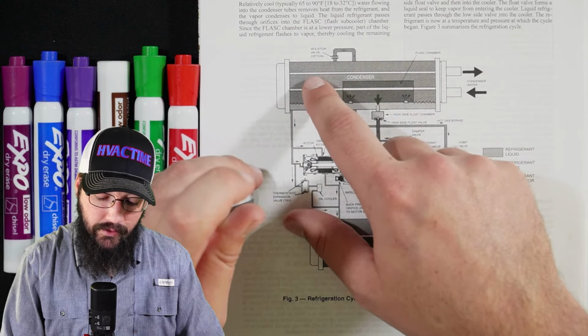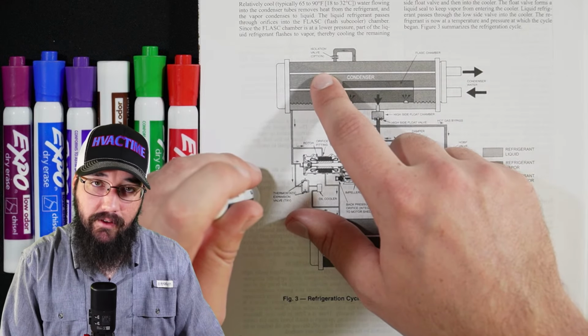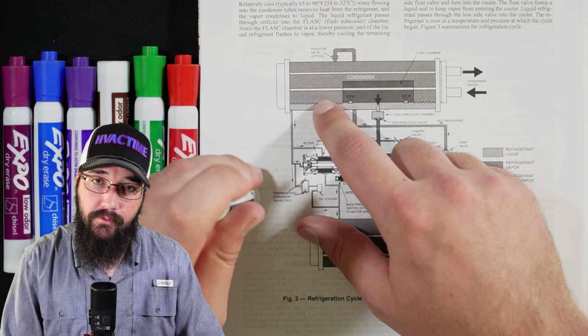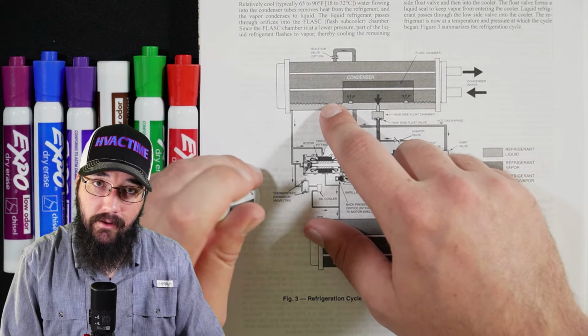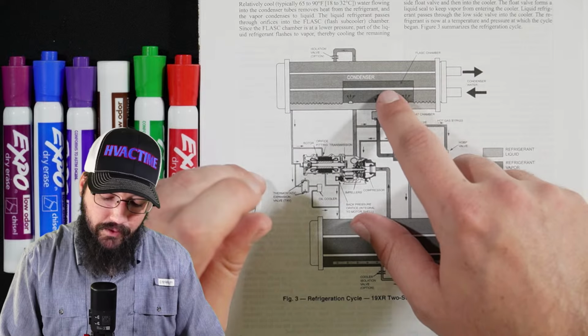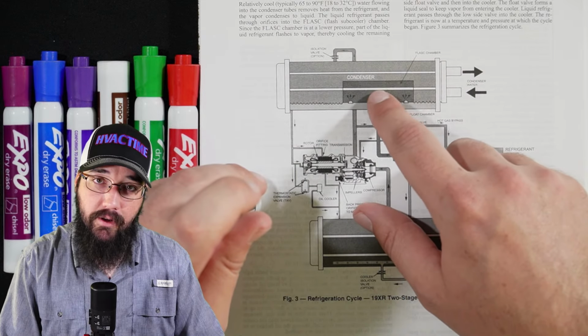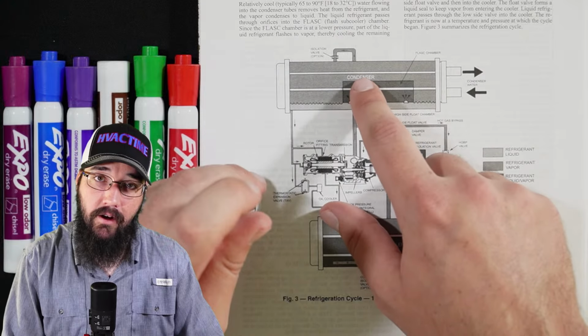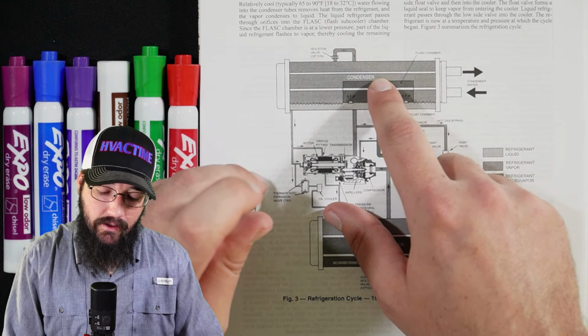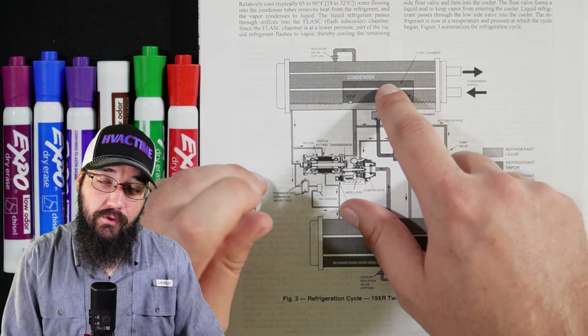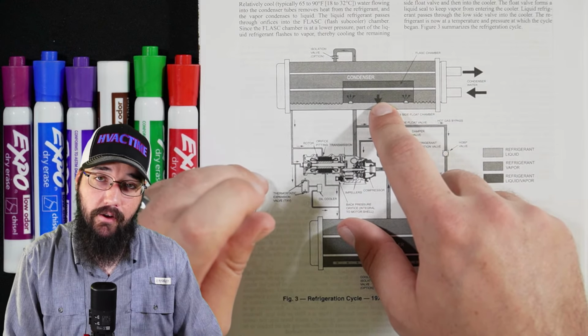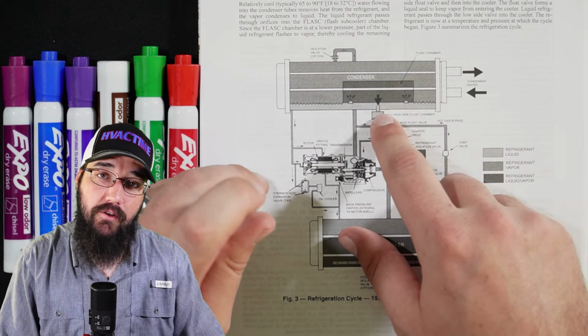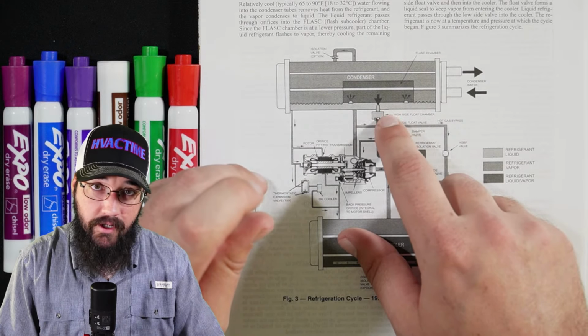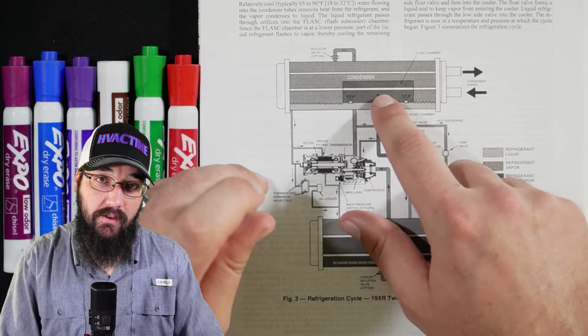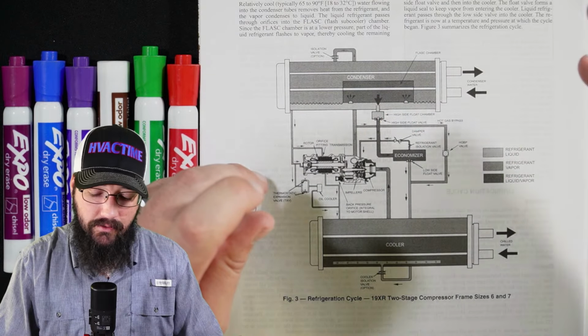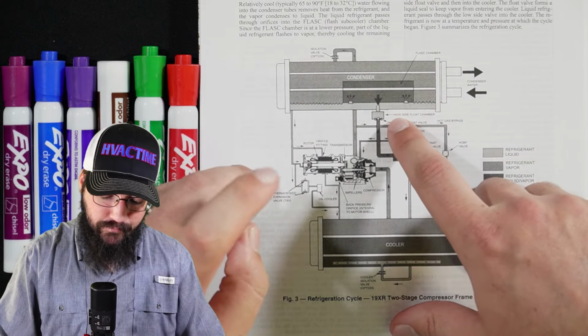So not only is the outside of this chamber condensing that liquid refrigerant down from a high pressure discharge gas to a high pressure liquid, but then we're also taking this medium pressure. We have a medium pressure liquid draining down, and we have a medium pressure gas inside of this chamber at the top. Those condenser tubes are then cooling that medium pressure down and allowing it to condense so that it drains into the float valve chamber as well. So you have both processes happening there simultaneously. It's a lot. So there's a lot happening.